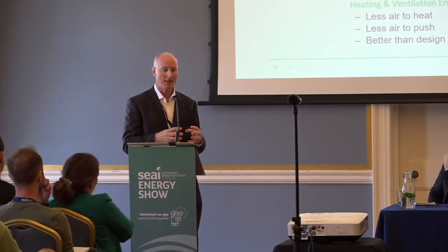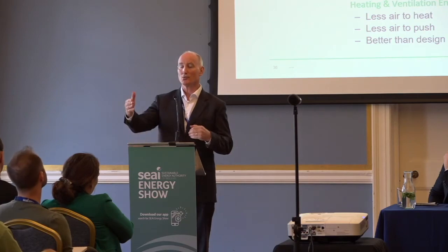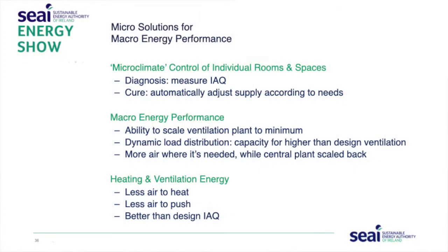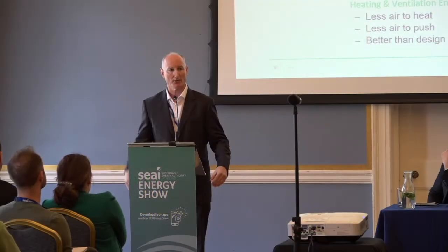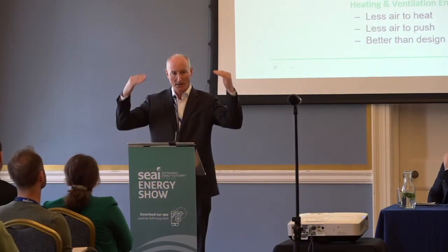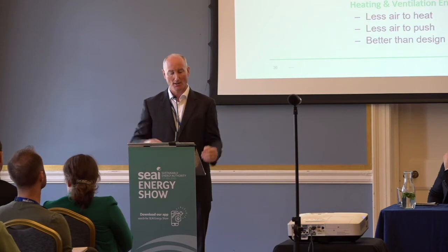So if you think of a building that's designed and commissioned, every meeting room, every office space has got a variable control damper commissioned to give the right amount of air, design quantity of air into that space. So if it's a 10-person meeting room, you've got 10 times 10, 100 litres per second designed to go into that space. That's there all the time. Likewise for the office space, 1 person per 10 square meters or 8 square meters, the ventilation is based on that, so that air is pushing through all the time.